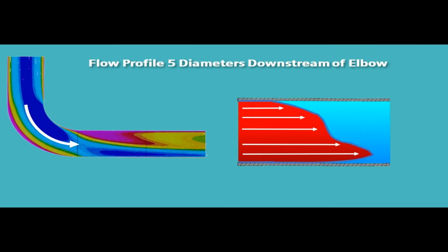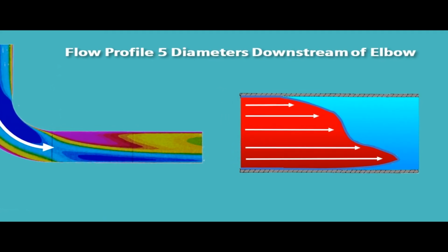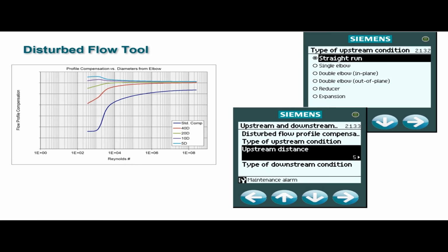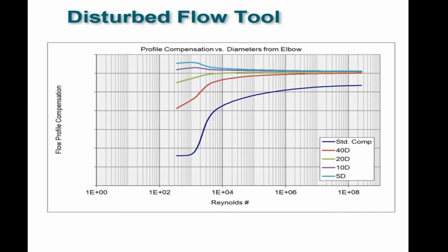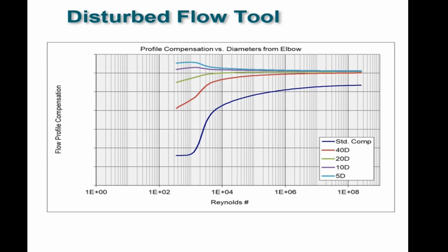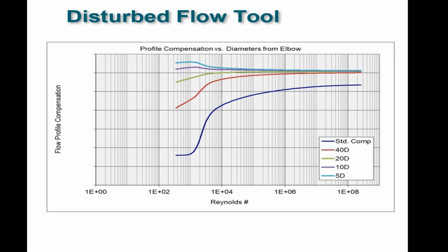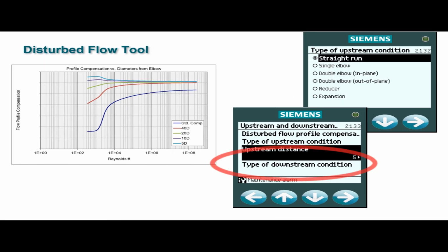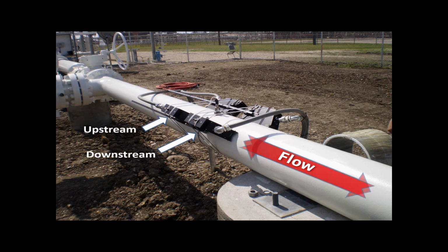This now leaves only the asymmetrical flow profile and its effect on Reynolds number to contend with. This was solved handily many years ago with an algorithm that we developed and patented. This feature, known as the disturbed flow tool, enables the user to program the upstream pipe geometry and the distance of straight run to the sensors. This information is used to calculate the theoretical flow profile and the required Reynolds number correction factor, which is then applied to the flow measurement. There is also a downstream straight run entry, which is useful in bidirectional flow applications. When flow reverses, what was downstream now becomes upstream.